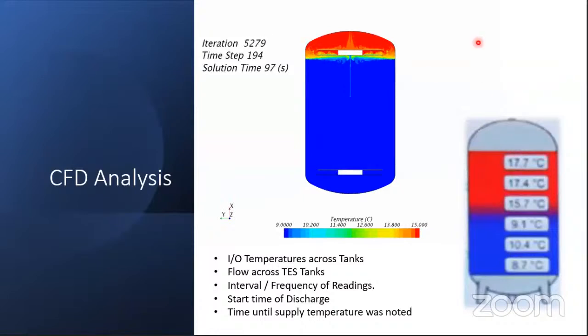To give you an idea about the CFD analysis, a CFD analysis is also conducted for these tanks to ensure the parameters considered will help stratification happen, whether or not the tank and the diffuser are designed appropriately. So this is one CFD analysis, and this is happening while discharging. The warm water is coming back from the top. The chilled water is being discharged from the bottom, and you see in between here there is a layer. There is a mixing happening here. It's a controlled mixing. That is a zone which is called the thermocline, which we will see in the slide coming.